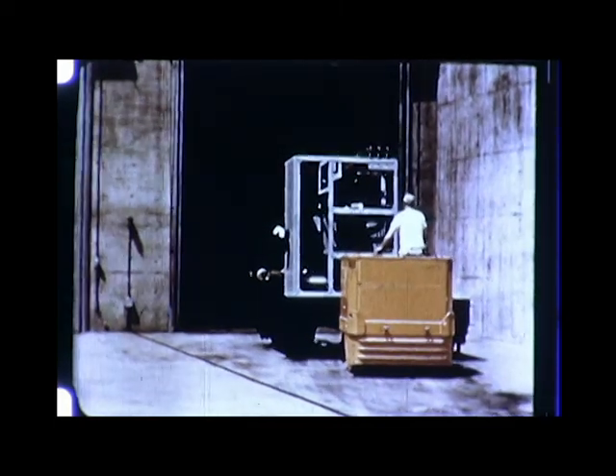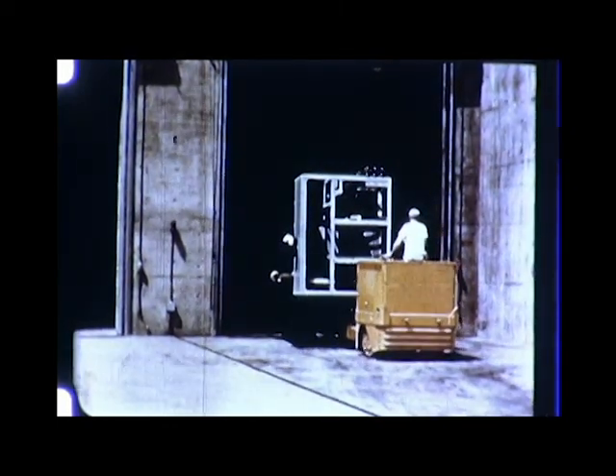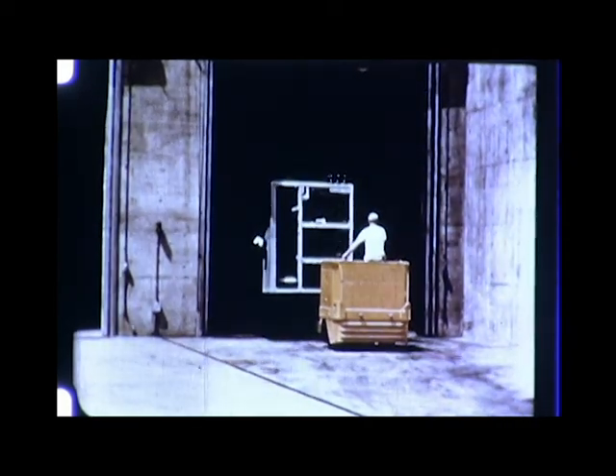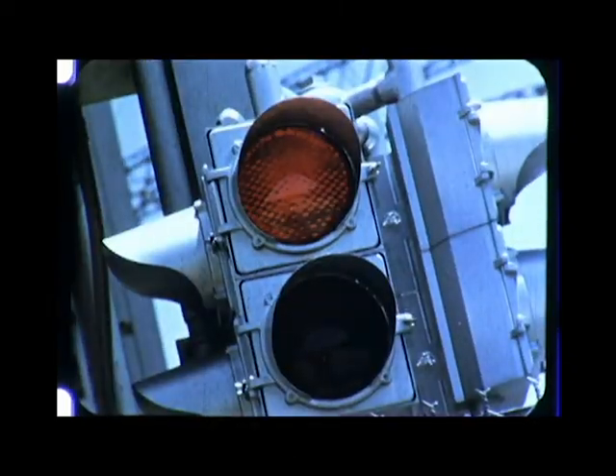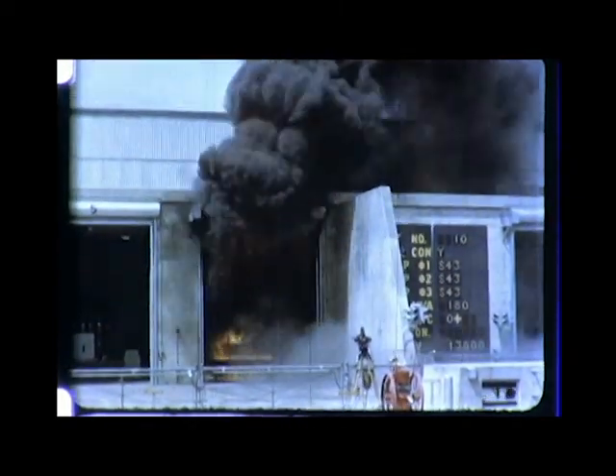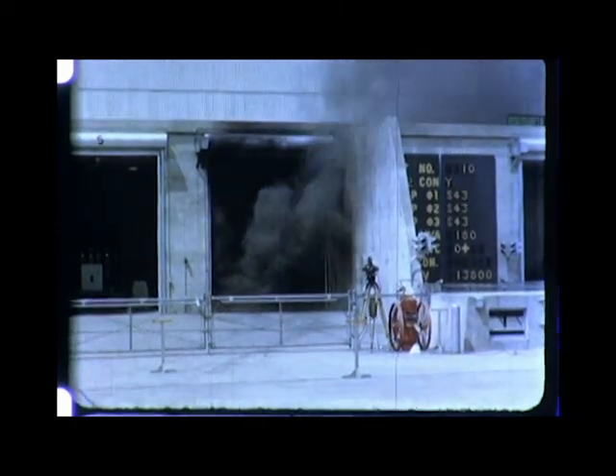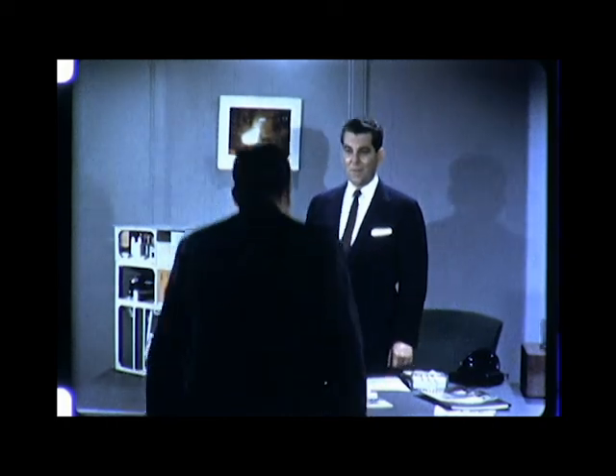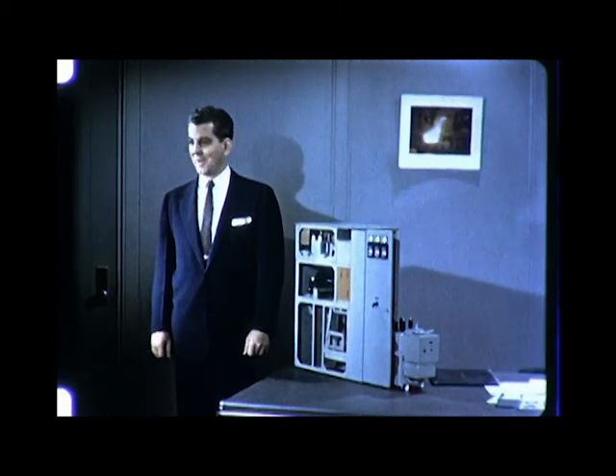By way of comparison, what about an older oil circuit breaker? In its day, this breaker had offered many years of good service. But can it handle the capacities that are found in today's power systems? Rated 90,000 kVA at 13,800 volts, it will be tested at 180,000 kVA. And then our meeting was finished. We exchanged a few closing remarks, and my visitor left. A couple of weeks later, his company invested in more new metal-clad switchgear.